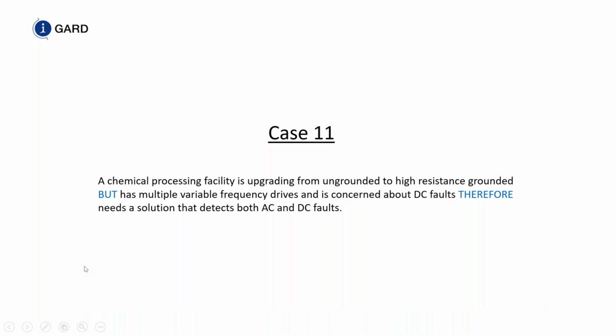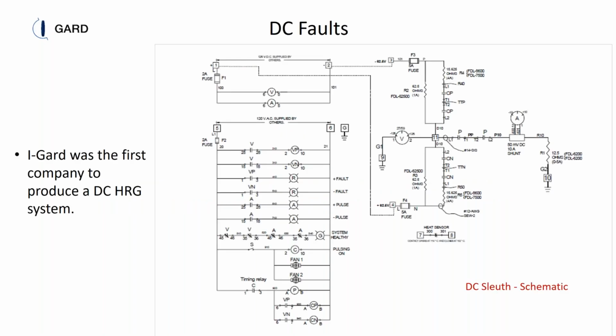Case 11: a chemical process facility is upgrading from an ungrounded to a high resistance grounded system, but has variable frequency drives and concern about DC faults. Therefore, they need a solution to detect both AC and DC faults. Well, I-Gard was the first company to come up with a DC Sleuth. We actually detected DC faults on pure battery systems, and here's a schematic for that.